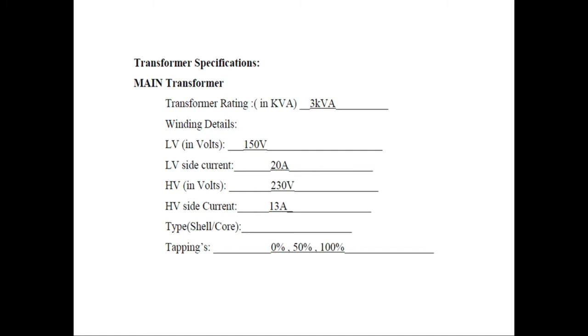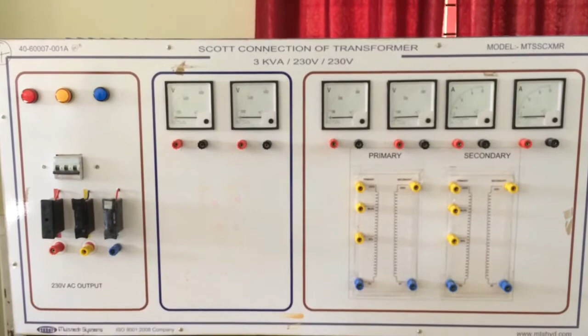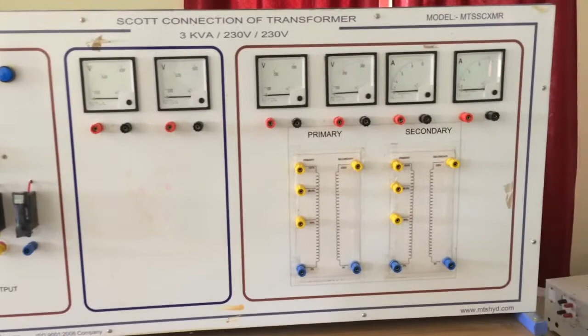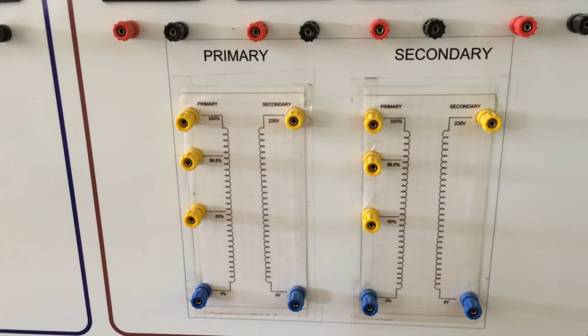Now we are going to see the panel board of the Scott connection of transformer. Conducting a Scott connection is nothing but converting a three-phase transformer into a two-phase transformer. For that we need two transformers, one called the teaser transformer and the other the main transformer. To perform the Scott connection, we need a teaser transformer that has tappings of 86.6% and 50% on both the primary as well as the secondary.